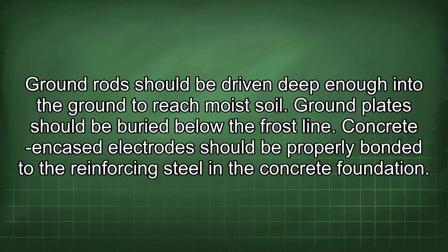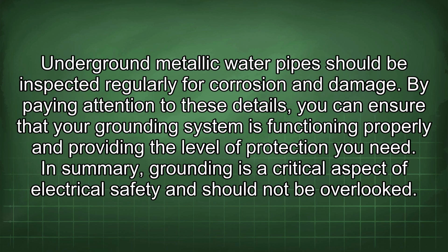Ground rods should be driven deep enough into the ground to reach moist soil. Ground plates should be buried below the frost line. Concrete encased electrodes should be properly bonded to the reinforcing steel in the concrete foundation. Underground metallic water pipes should be inspected regularly for corrosion and damage. By paying attention to these details, you can ensure that your grounding system is functioning properly and providing the level of protection you need. In summary, grounding is a critical aspect of electrical safety and should not be overlooked.